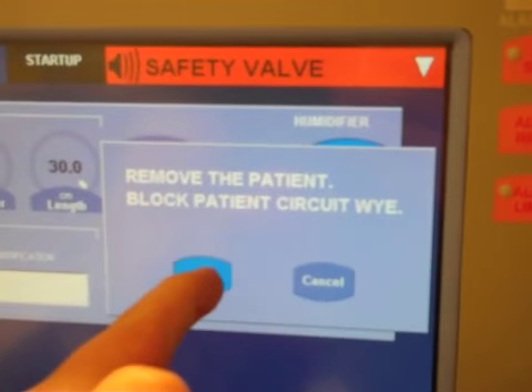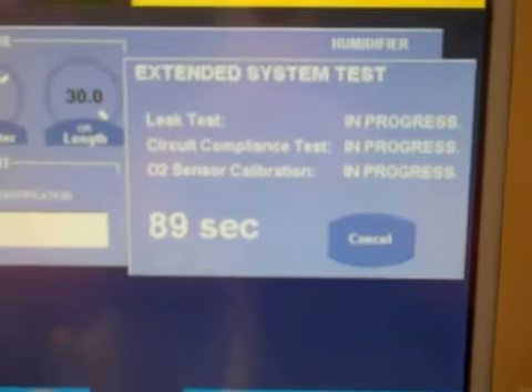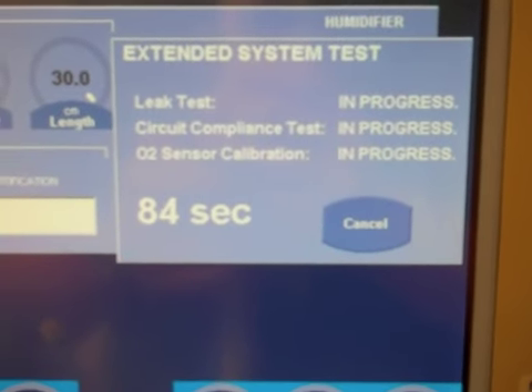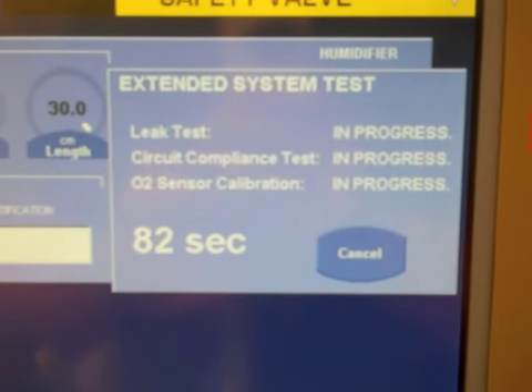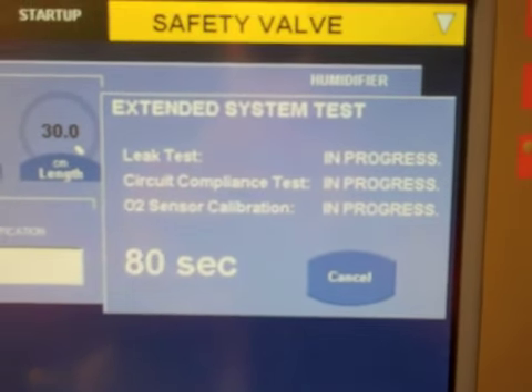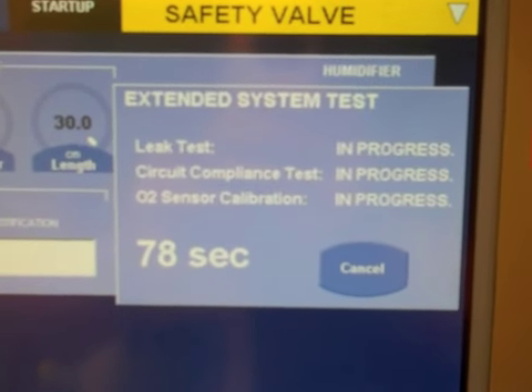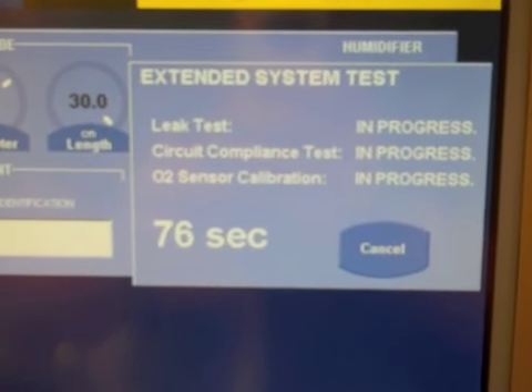I'm just going to use my hand here, so if you're in the clinic you can use the blue cap or a sterile or a clean glove. This takes roughly 90 seconds. You're going to see it's going to go through a leak test, a circuit compliance test, and an oxygen sensor calibration. I'm going to stop the video at this point and pick back up when our test is passed.